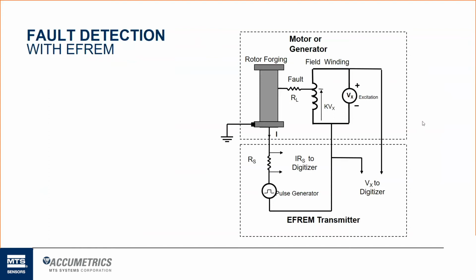So that way it eliminates that issue where the fault needs to be much more severe at the negative side versus the positive. It basically balances that out and makes it a much more accurate measurement between those 2 points on the field windings itself.